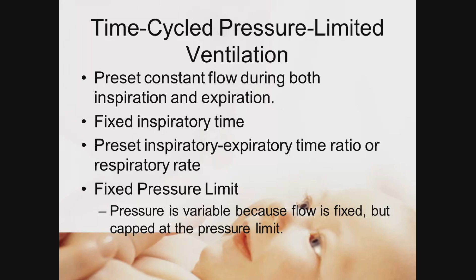It's not like pressure control, where you have an expansive amount of flow available. This is one where it's a fixed flow rate that we set as part of the setup. It's time cycled, and then you set the flow rate, because I'm not delivering a fixed volume. Depending upon compliance and resistance, the volume will change. Unlike in a volume-based breath, when compliance and resistance change, the volume stays constant.